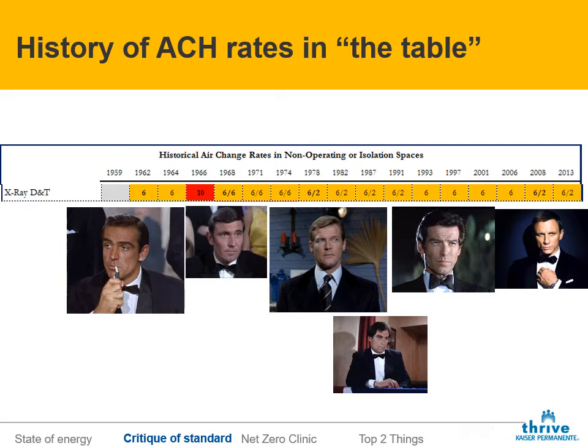But in the B occupancy buildings, there's no code requirement for 6 air changes. And so we tend to not use this number. We build those buildings with VAV systems and return air plenums all the time. So we have thousands of examples of X-ray rooms where we didn't use 6 air changes per hour, and there's really no reason to, right? But in our national standard, we still have that number, right? Because again, it's largely driven by the votes, and the committee is kind of conservative. We've always published the number that said 6 air changes per hour, so we might as well just keep it, right?